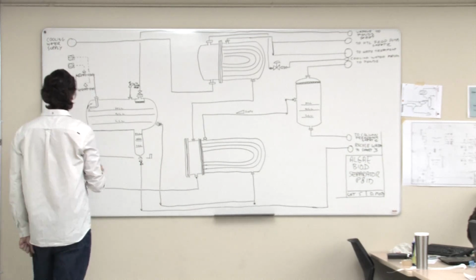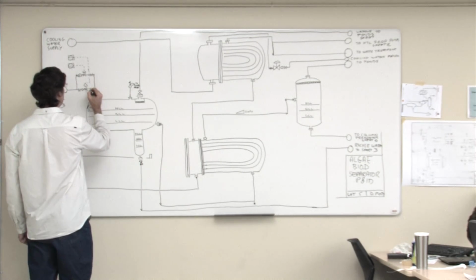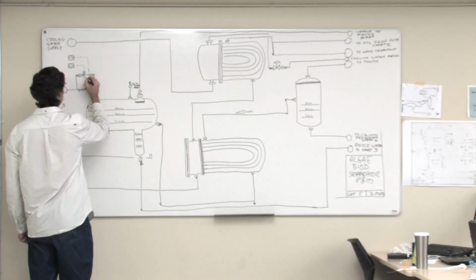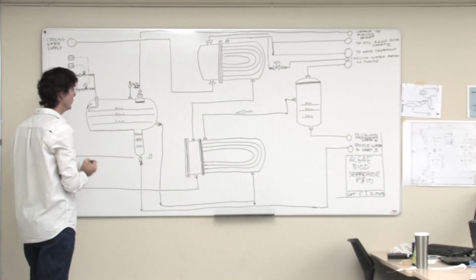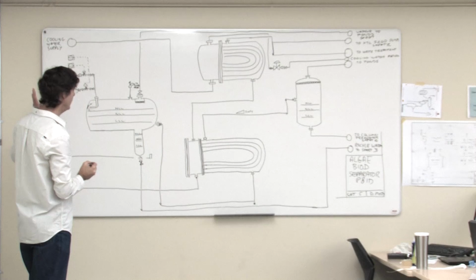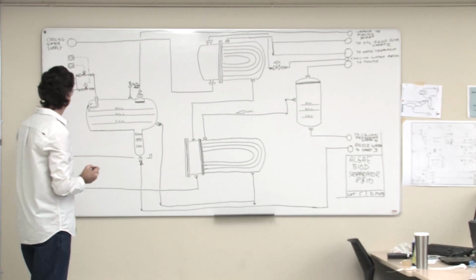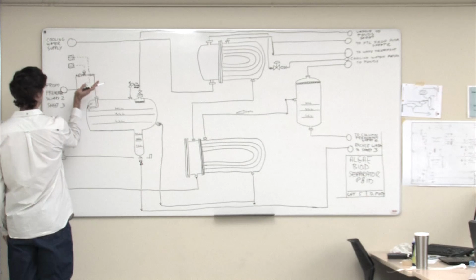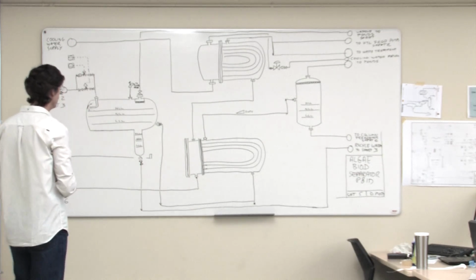Probably the best thing to do would be to make these valves fail closed, I think. If we have a problem, the last thing we want to do is start dumping 3,000 psi high temperature, almost subcritical water into that vessel. So I want to bottle the problems up back here.